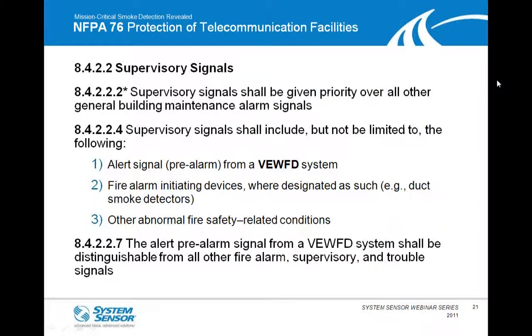So moving ahead, again, continuing with NFPA 76. Now we're in 8.4.2.2. This is where we're talking about supervisory signals. Supervisory signals shall be given priority over all other general building maintenance alarm signals. So we already talked about fire taking the priority. Supervisory also we want to take priority over any kind of general building alarm signals.